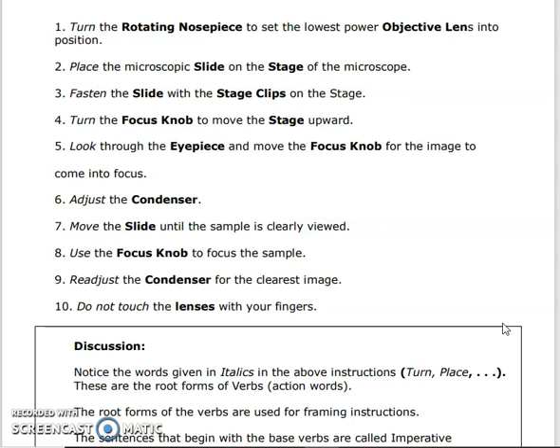Third, fasten the slide with the stage clips on the stage and adjust the stage clips to correct the position. Then turn the focus knob to move the stage upward. Look through the eyepiece and move the focus knob for the image to come into focus. Adjust the condenser. Move the slide until the sample is clearly viewed. Use the focus knob to focus the sample. Re-adjust the condenser for the clearest image. Do not touch the lenses with your fingers.